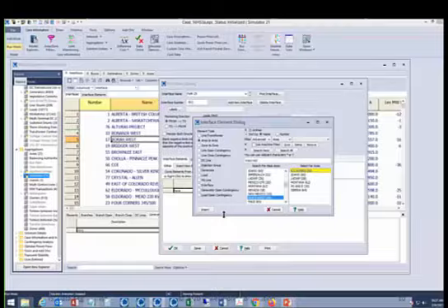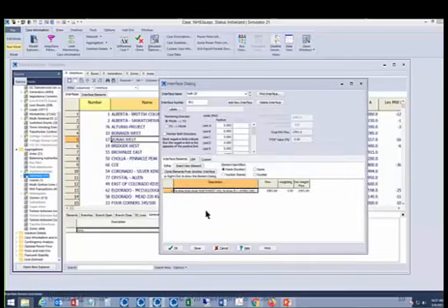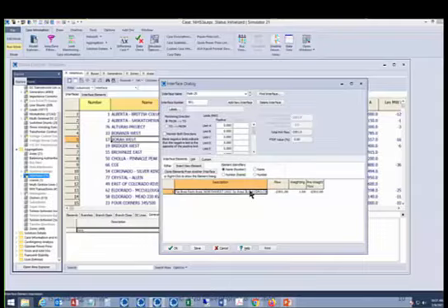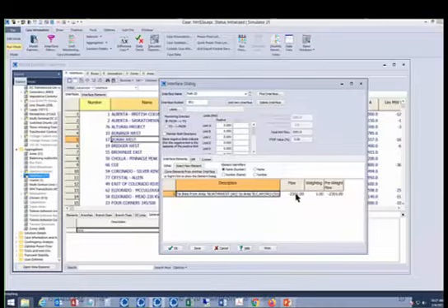If you go into your case and you create a new tie line or you remove one that was there before, then the definition will change with it. It's just grabbing everything. It's like a pointer that grabs everything that fits that description. So that's one item. I'll go ahead and insert that, and then it'll calculate the flow. So what this tells me is, in this case right now, there's actually 2,300 megawatts going from BC Hydro to Northwest, which is why that's negative.